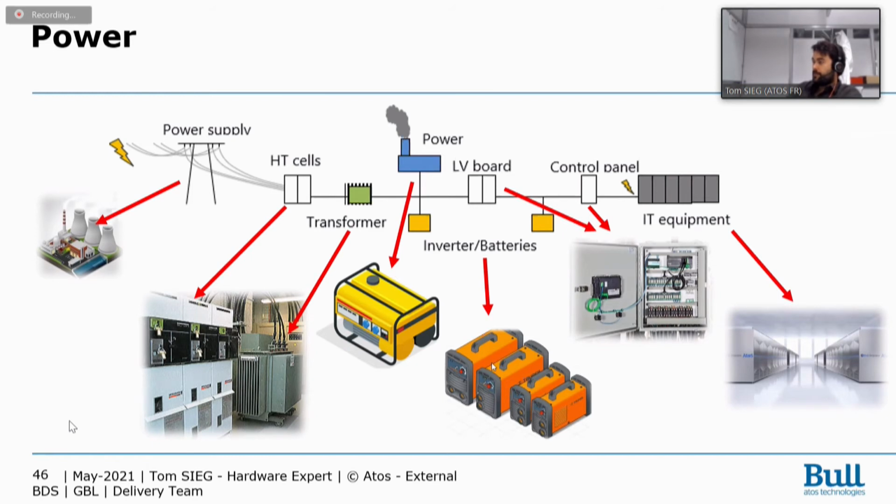If you have a really big room with a lot of inverters and batteries, you will maybe be able to maintain electricity during 1, 2, 3 hours. Some battery rooms can maintain electricity during 1 day. Don't forget that an HPC cluster will consume a lot of electricity. So you have to adapt, of course, your inverter and battery between 2 points: how much time you want to maintain your services, and the price.